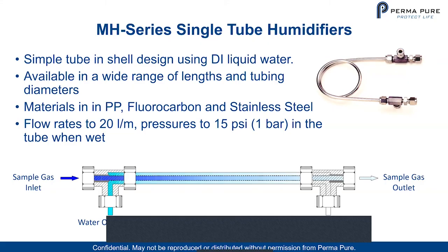And here you can see a similar diagram to our MD, except we have the sample gas going through the inside of the tube and your water going on the outside of the tube. Sometimes we do that in the opposite way, where we have the water on the inside of the tube and the gas going on the outside of the tube. They both work.